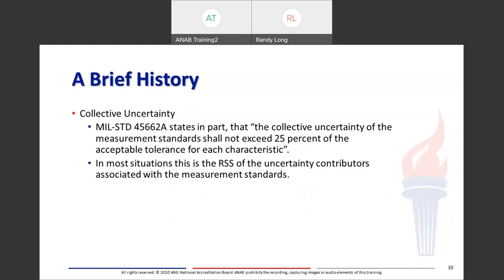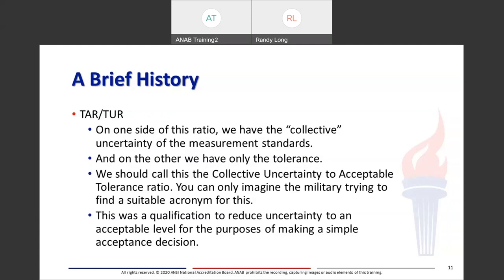MIL-Standard 45662, which was rescinded in 1994, stated in part that the collective uncertainty of the measurement standards shall not exceed 25% of the acceptable tolerance for each characteristic. In most situations this was a root sum square of the uncertainty contributors associated with the measurement standard. On one side of the TAR/TUR ratio you've got the collective uncertainty of the measurement standards, and on the other, only the tolerance of the unit under test or equipment for calibration. This was a qualification to reduce uncertainty to an acceptable level for the purposes of making a simple acceptance decision.